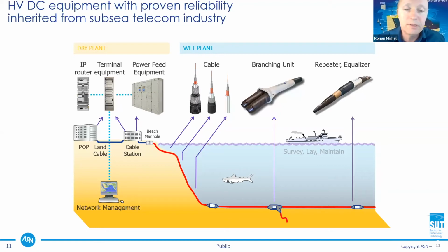What is probably worth saying here is that the optical amplifiers are put in series on the cable. On these systems, we energize the optical amplifiers from the copper on the cable. You can see the copper on the cable here. It is a single copper cable. We feed 1 amp constant current on these systems, and then the voltage builds up per the number of amplifiers and the distance, which is the ohmic losses on the cable.